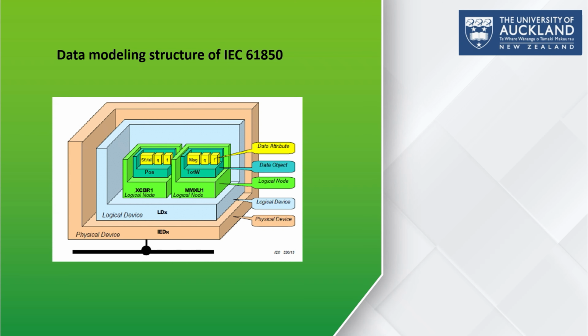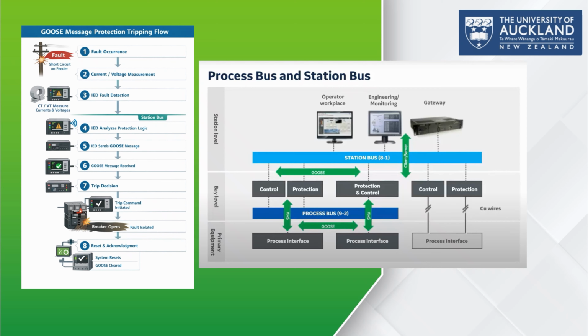So what is GOOSE messaging? GOOSE stands for Generic Object Oriented Substation Event. It is a communication method defined under IEC 61850, allowing protection and control IEDs in a digital substation to exchange important status information and trip signals quickly and reliably using an Ethernet network. Instead of relying on the traditional hardware copper connection between the relays, breakers, and protection panels, GOOSE enables these signals to be sent directly over the network. This means fewer wires, faster response, and a smarter substation.